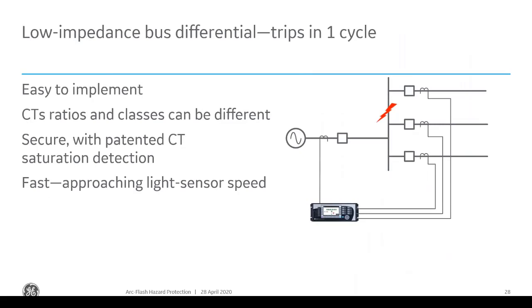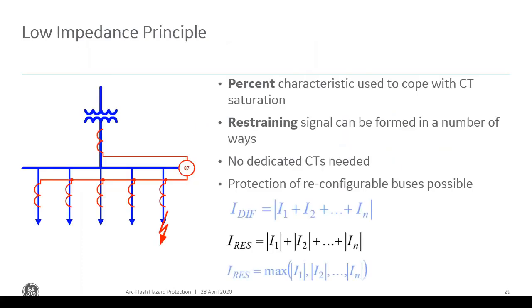But how it works is basically Kirchhoff's current law: current into a node should equal current out of a node. So that's what it does. All the CTs are connected directly into the relay, unlike the high impedance scheme where they're in parallel. So you can monitor the CTs individually. If you have a problem with the system, you can tell if there's a problem with one of the CTs. It has techniques built into the algorithm to mitigate the effects of CT saturation. So it's very secure and very fast.